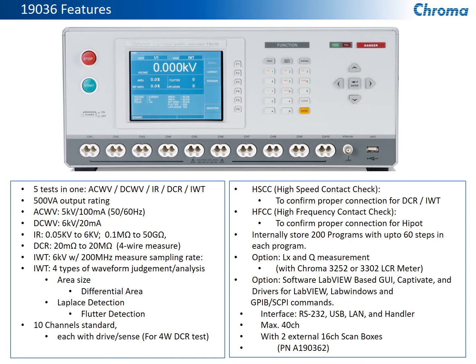It goes up to 5,000 volts AC, up to 6,000 volts DC, 100 milliamps AC, 20 milliamps DC for high voltage withstand voltage testing and/or hipot testing. Insulation resistance all the way up to 50 gigohms. DC resistance measurements down to the lowest ranges in the 20 milliohm range, which gives you measurements reliably down below 1 milliohm. Impulse winding testing up to 6,000 volts does a great job, with a 200 megahertz measurement sampling rate of the data points that make up the waveforms. We'll talk about that a little bit later in this presentation.